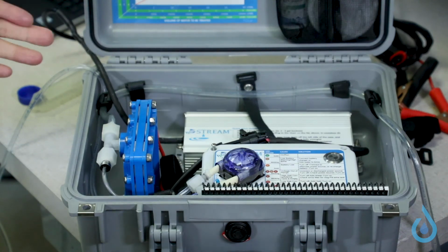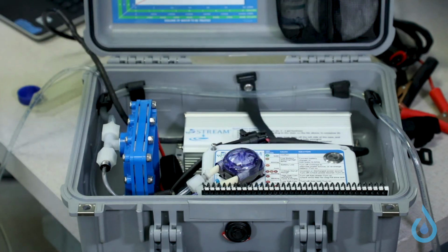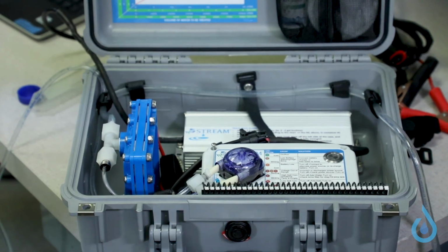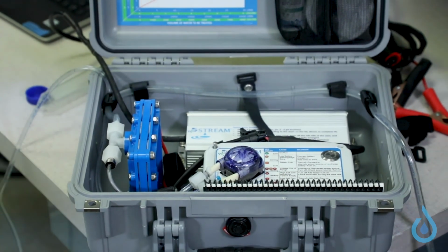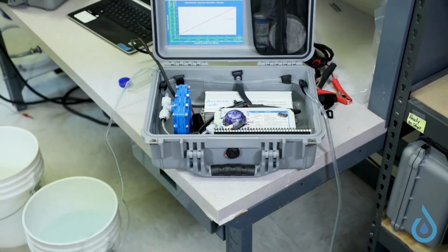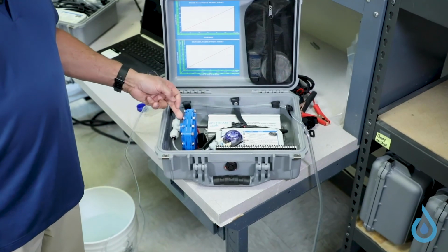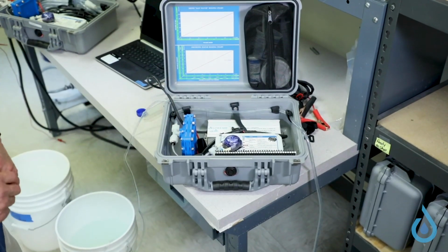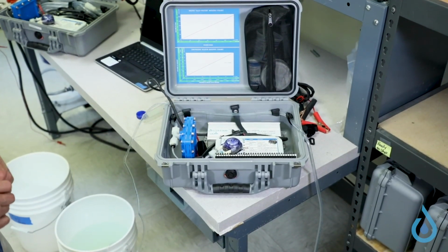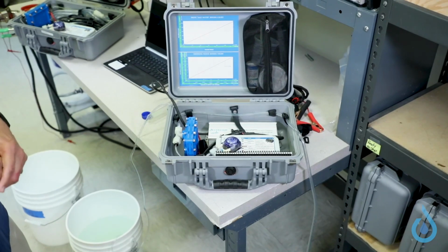So when that occurs, if it was simply a brine tank running out of brine, then that's usually the problem. But if the brine tank has brine in it and it's been running, and you see white calcium forming in the tubing or fitting, it's time to acid wash the system. And we'll cover acid washing in a separate segment.